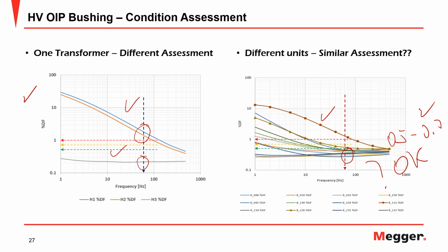But now I am able to put all those bushings under the same spectrum and do some comparative analysis, bringing those normalized to 20 degrees C by ITC, not by just a reference table or a reference chart, but looking into the unique dielectric response that each one represents. As you can see, on the 60 Hertz, you barely see any differences.